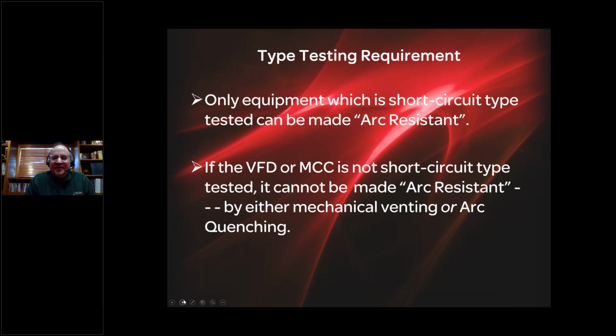So in terms of what we can protect, I need to make an important point. Only equipment which is short circuit type tested can, by definition, be made arc resistant. So if the VFD or motor control center is not short circuit type tested, it doesn't have an interrupting or withstand rating. It cannot be made arc resistant either by mechanical venting or arc quenching means. Now, of course, all modern MCCs that you would buy from any major manufacturer would be type tested, as would any panel board.